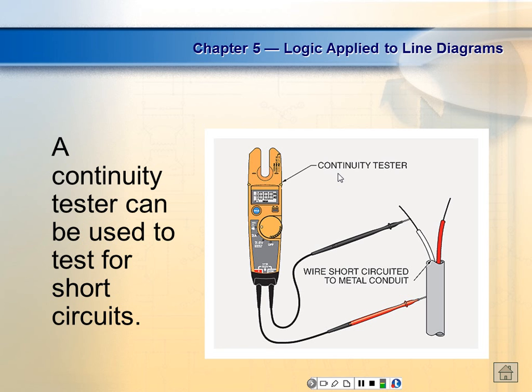We have a lot of people that blow fuses. They measure amps, and then they go to volts and they forget to switch their meter over to volts and they blow the fuse in the meter. We're not going to do any amp measurements. Your predominant meters are your ohmmeter and your voltmeter. The clamp-on is really neat, but clamp-ons normally only work with AC, and they work with high current AC.